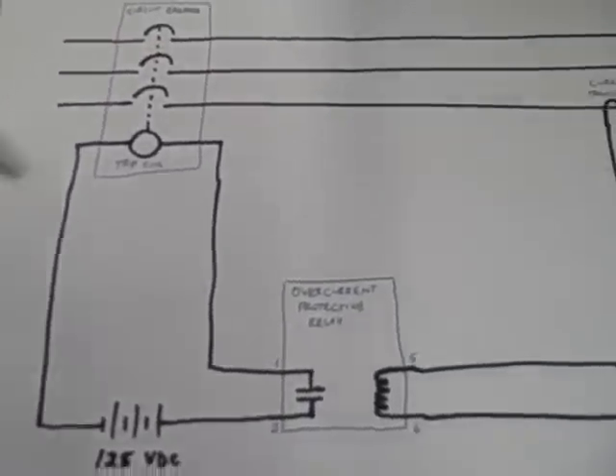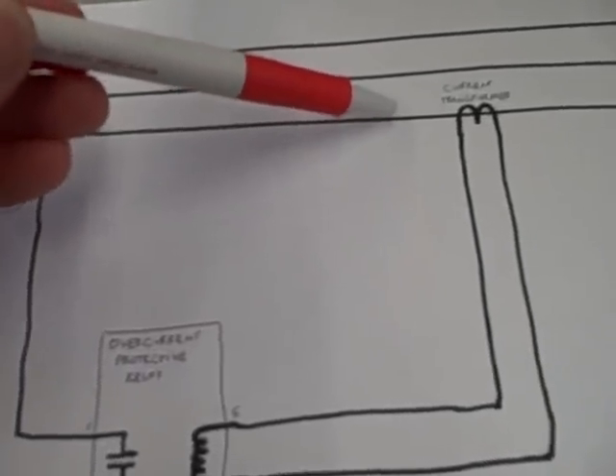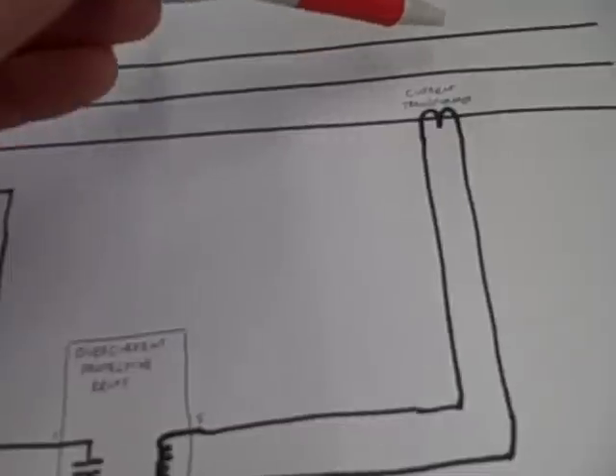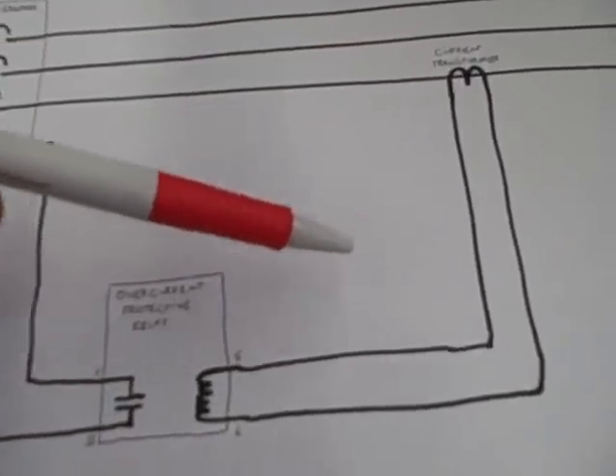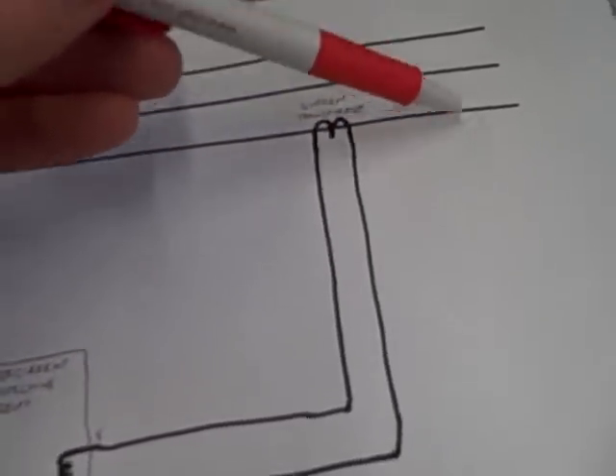What I have shown here is a protective relay system that's only monitoring current on one of the phase wires. Typically, we'd have three of these, monitoring current on all three phase wires, and sometimes monitoring the zero-sequence current on all three summed together.